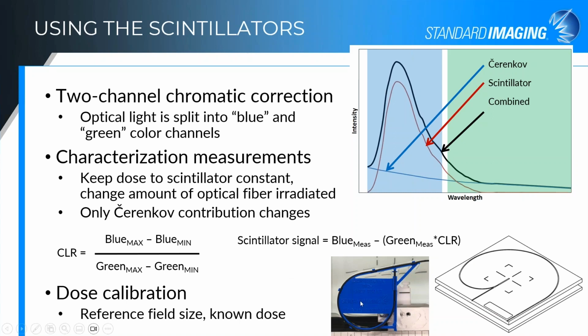Just a couple examples. This is the smaller jig that we include automatically with the W2 to do your CLR correction measurements in your water tank. So your minimum fiber configuration would have the fiber coming straight out, maximum has it wrapping around, and this fits within a 10 by 10 field. It's not centered in the field, but really that's not critical.